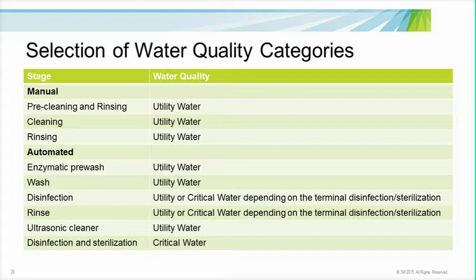We had a few questions regarding this on the previous webinar, and I wanted to clarify this in the fact that the TIR34 states that the water for the final rinse is dependent on the category of medical device, and that the written IFU should be consulted before to determine the exact quality of water that should be used for rinsing the device. It says some manufacturers of medical washers and medical washer disinfectors recommend tap water be used for the initial rinse, followed by deionized or purified rinse for the final rinse of all categories of instruments.